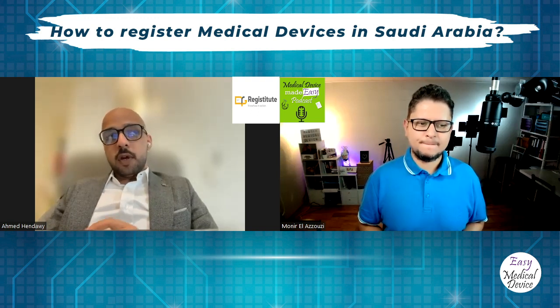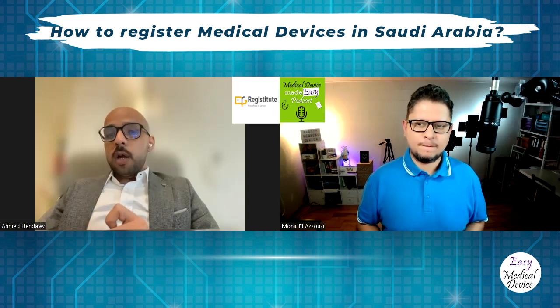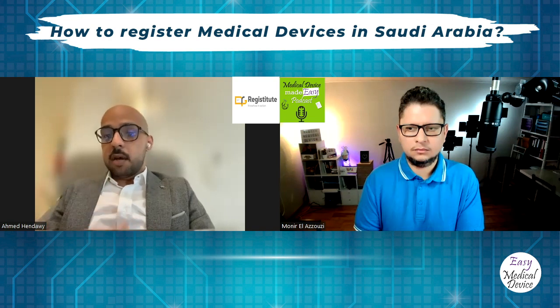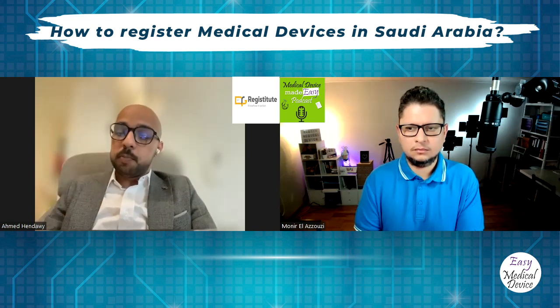One thing to note, though, is that for class one products, SFDA is not that insistent on providing the full requirements of the technical file, because they know that class one or low-risk devices usually don't have all the technical files or documents available. So there are possibilities of providing letters stating these documents are not available because it's a class one product. The requirements are the same, but you don't have to provide each and every one of them. If you don't have them, you just provide a justification to SFDA, and upon their approval, we can proceed with the application.